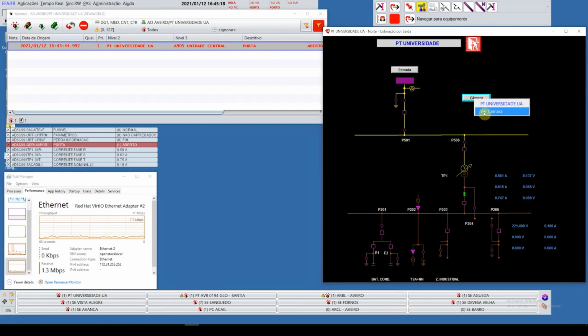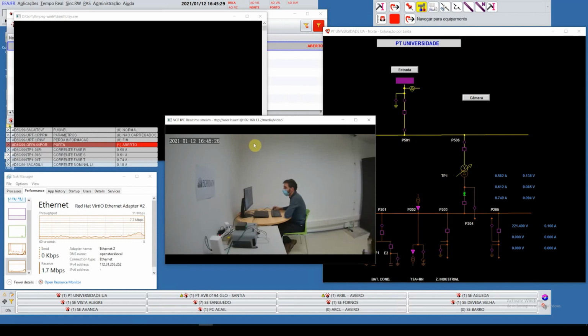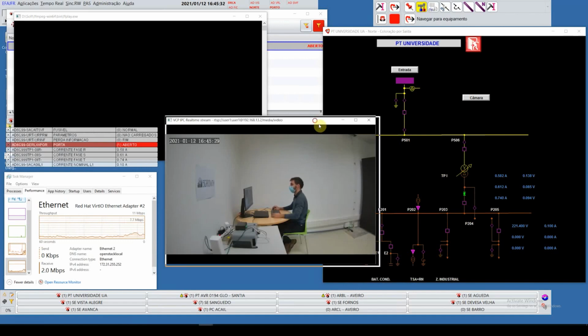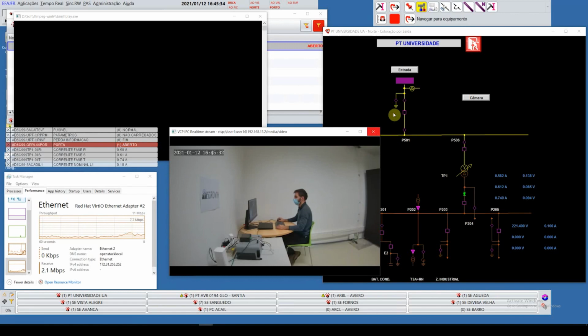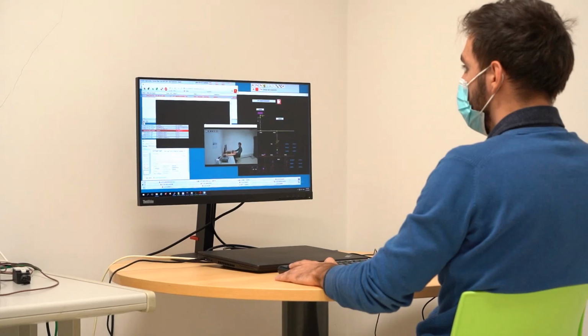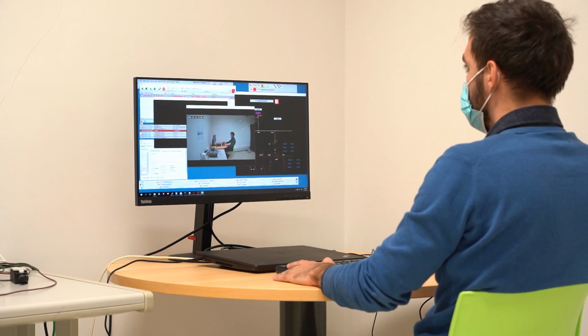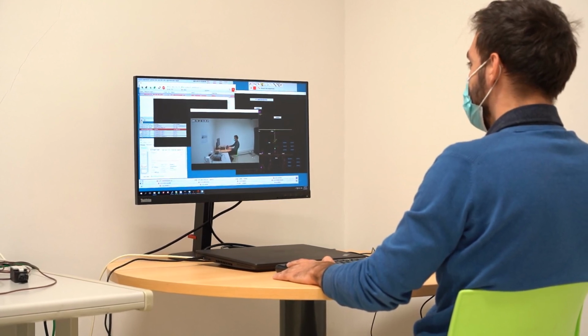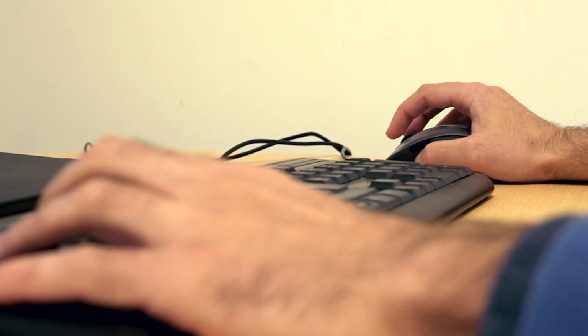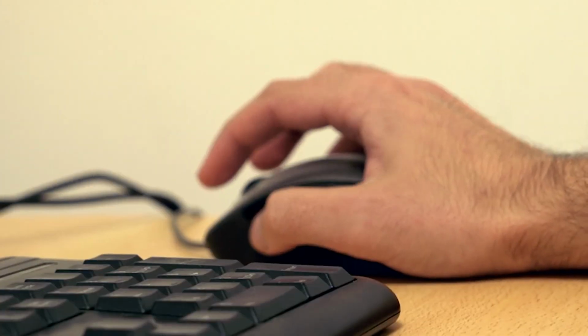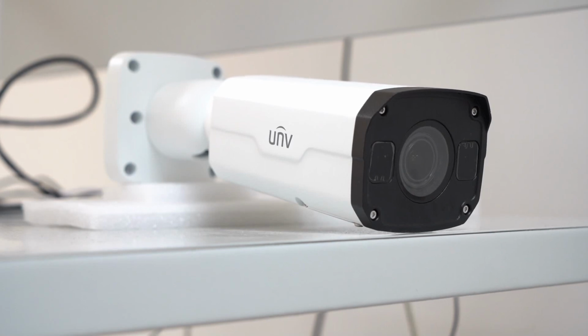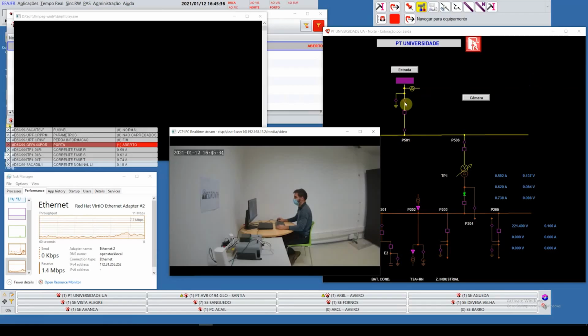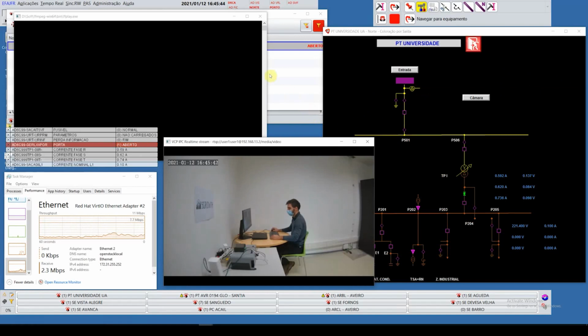The operator will then be able to open a video streaming transmitting from inside the substation to get further information about the root cause of the abnormal event. This can be particularly useful to the operator assessing what is going on inside the substation. Maybe a fire on the power transformer or a human or animal intrusion. He can then pass accurate information to the maintenance team on the field, saving valuable time preparing the intervention to resolve the occurrence. We can see that the throughput in the 5G connection is now considerably higher due to the video streaming being transmitted to the control center.